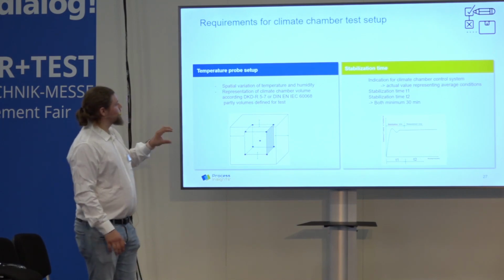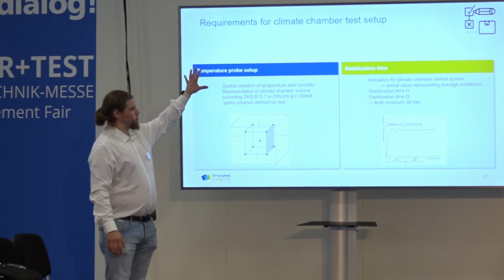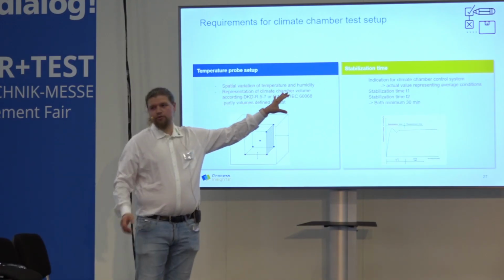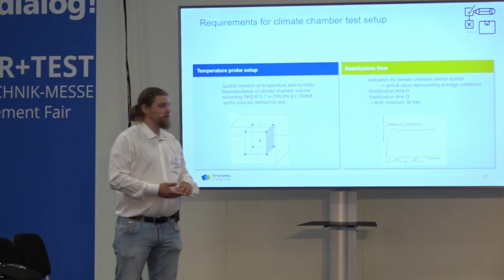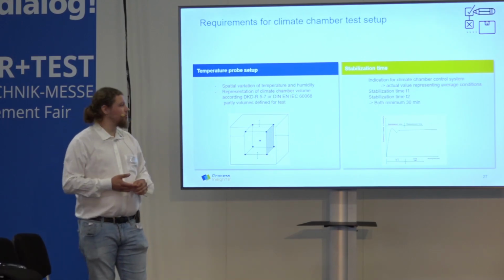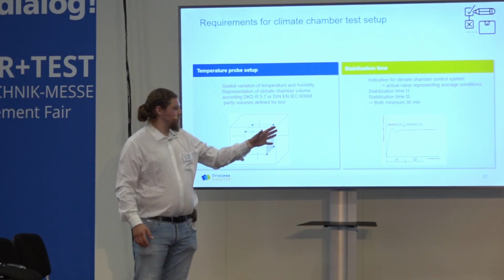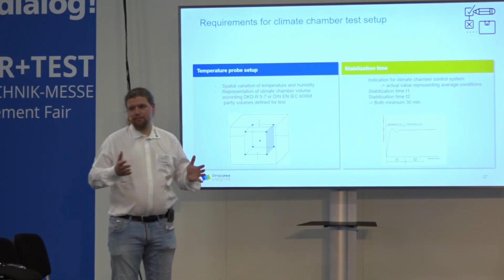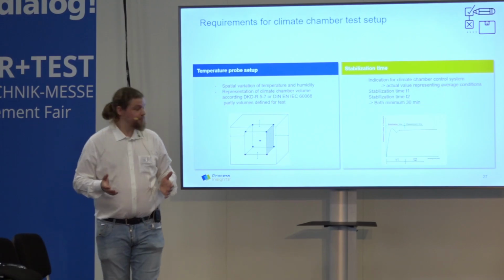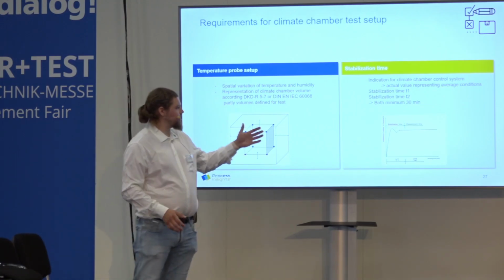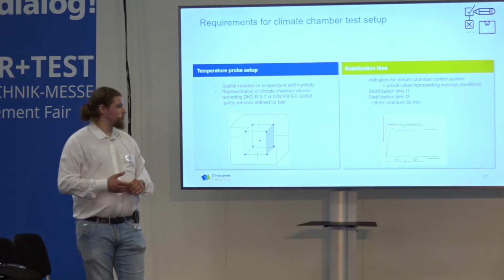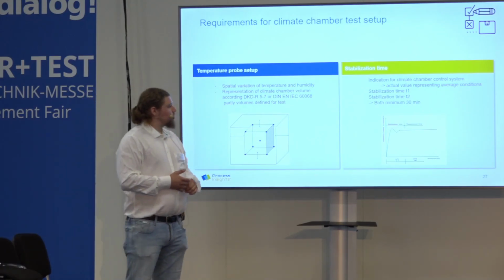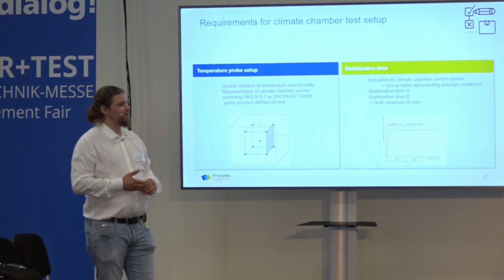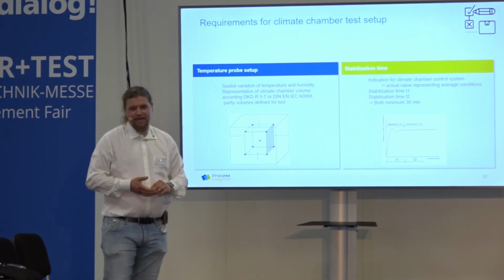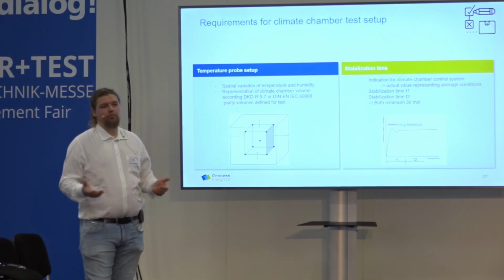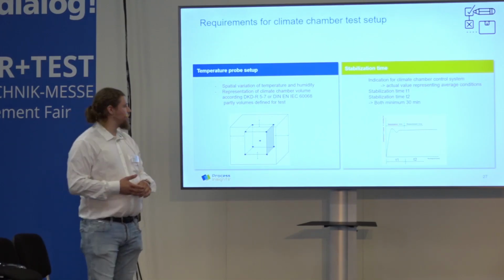The second important thing, after where to put the probes, and important for the next slide, is the stabilization time. A climate chamber testing procedure is split in two parts. The first is a stabilization time, which is defined to be a minimum of 30 minutes, and then we have the measurement time, which also is a minimum of 30 minutes. This is important for the application we want to introduce, which is a new opportunity for working with climate chamber calibration.